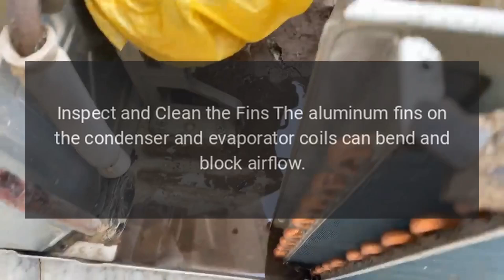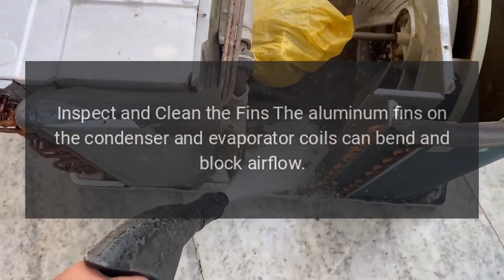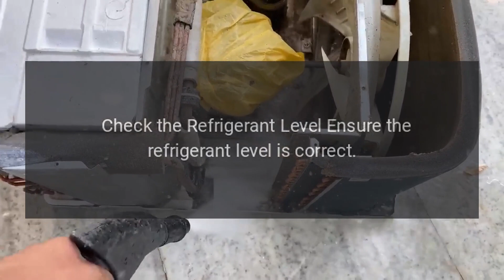Annual tasks: inspect and clean the fins. The aluminum fins on the condenser and evaporator coils can bend and block airflow. Use a fin comb to clean and straighten them. Check the refrigerant level. Ensure the refrigerant level is correct. Low refrigerant can decrease efficiency and damage the compressor.